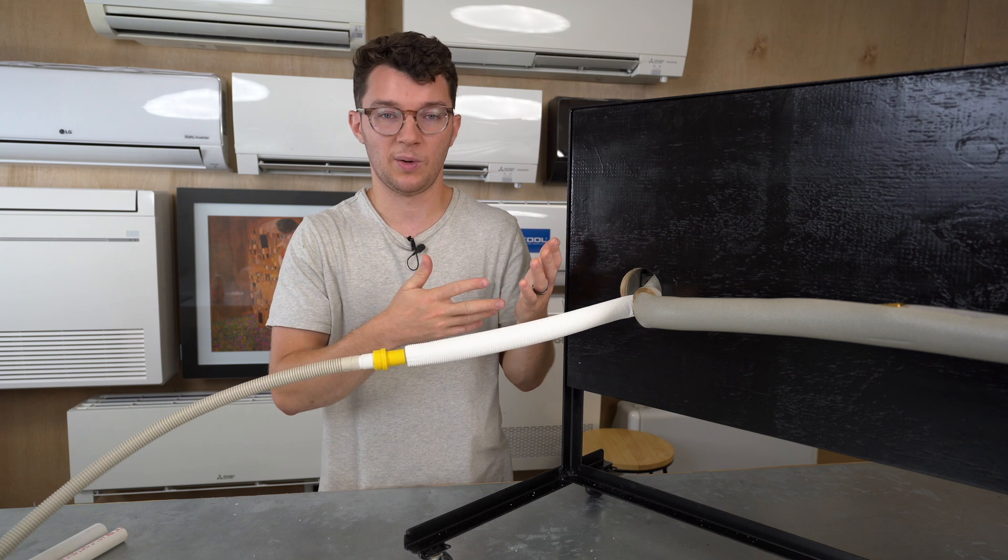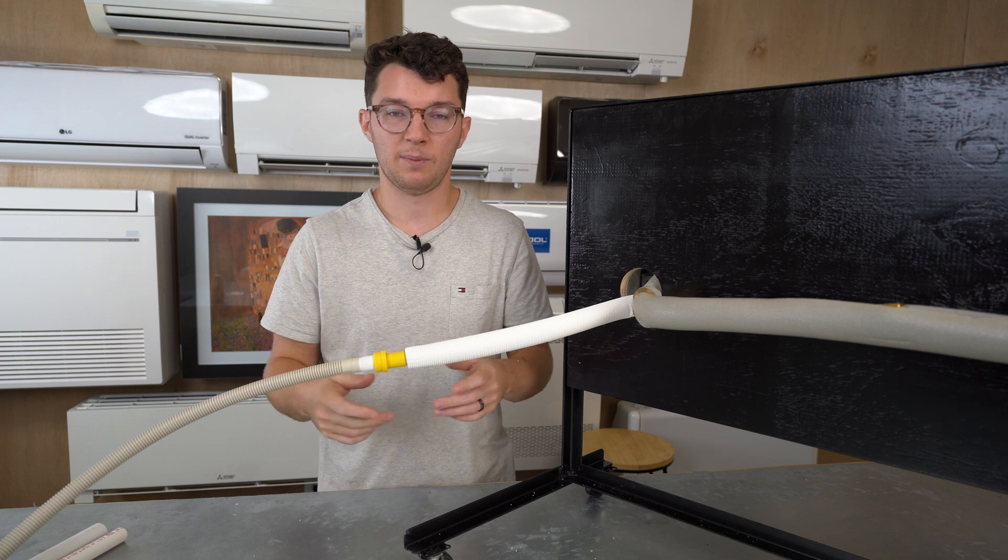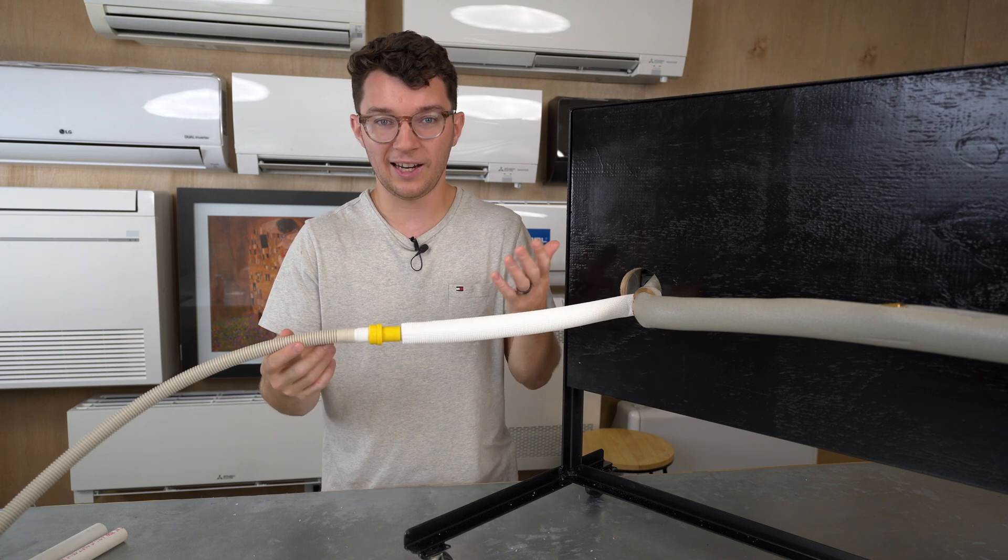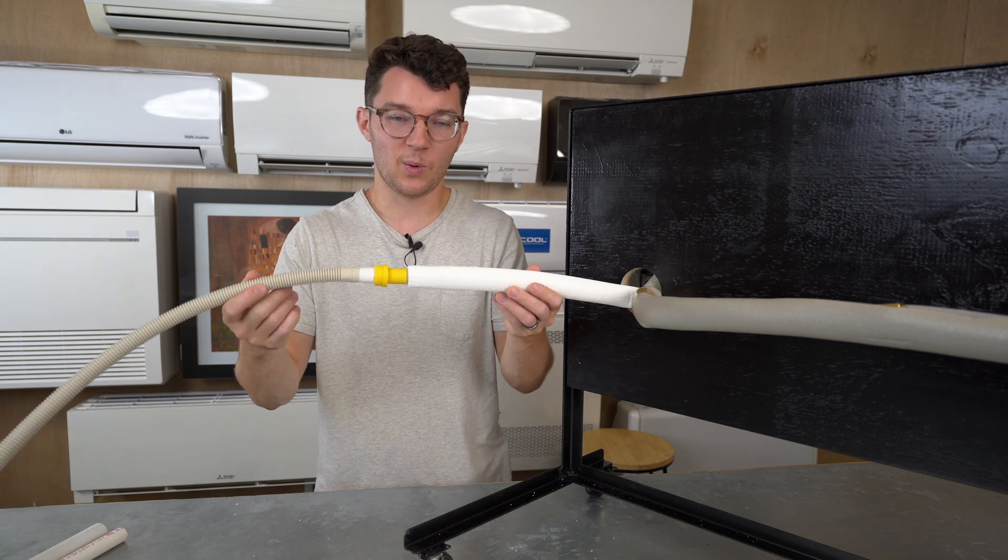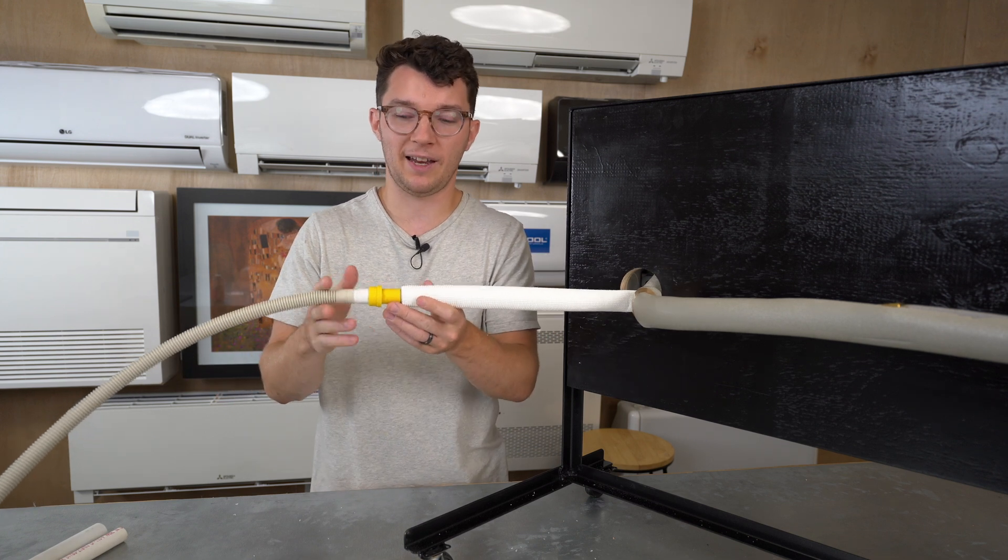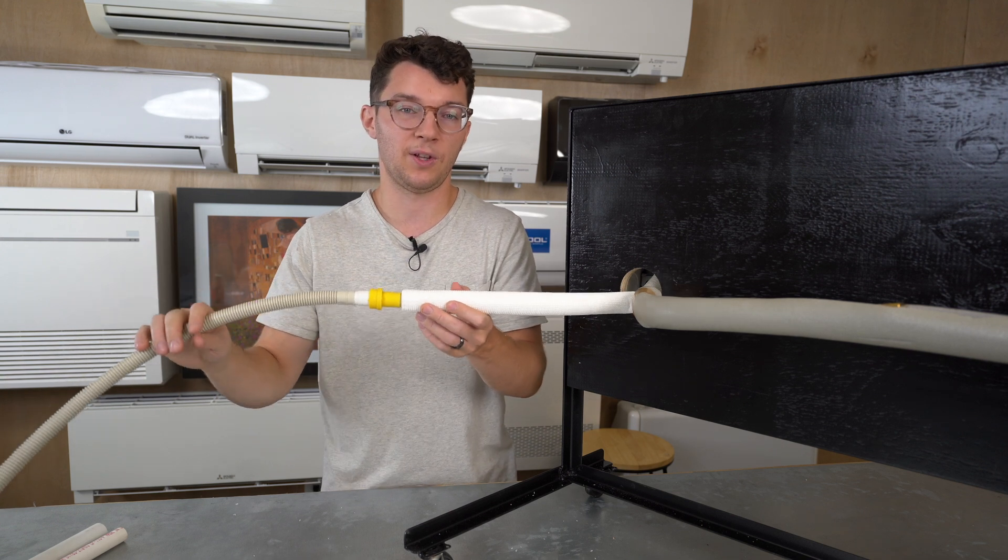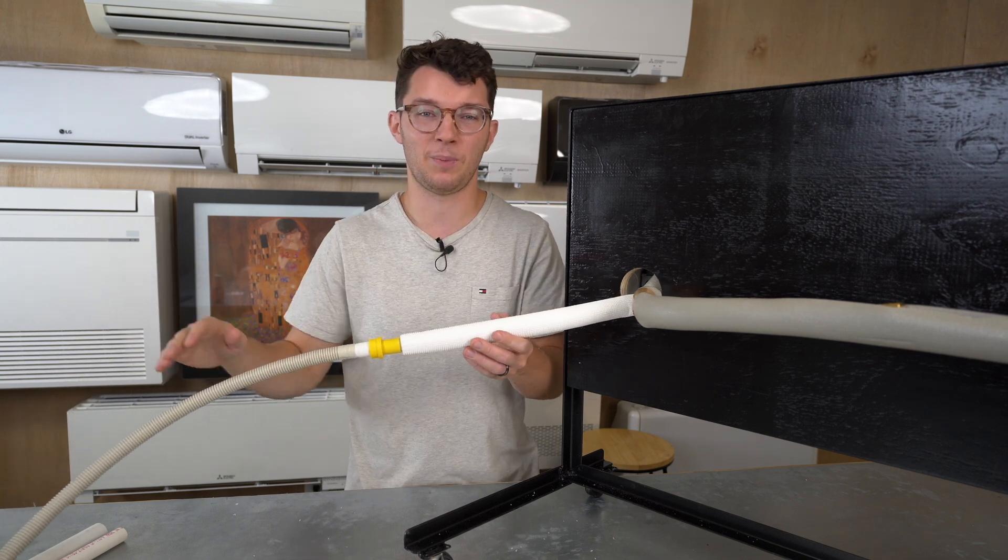It doesn't want to overflow the drain pan and then have a flood in the room, so it's going to shut off the indoor unit causing an inconvenience. When you're running a horizontal line, make sure that you have enough slope and you're clamping it as much as possibly needed to make sure you don't have any droops or ebbs and flows in that line. It's constantly sloping downward.